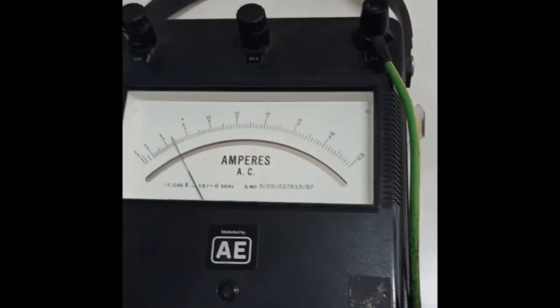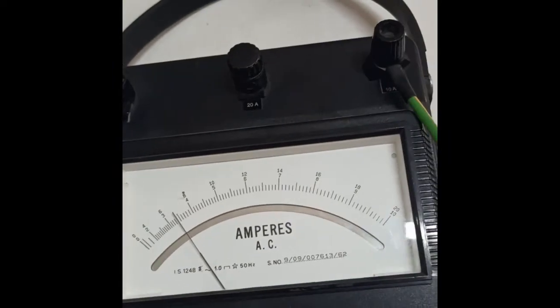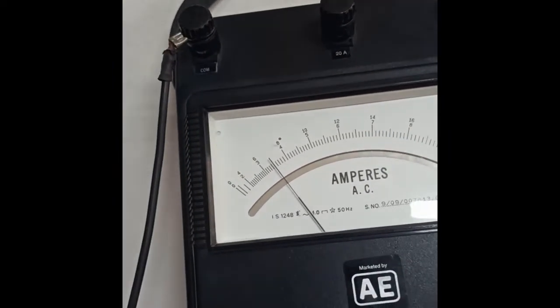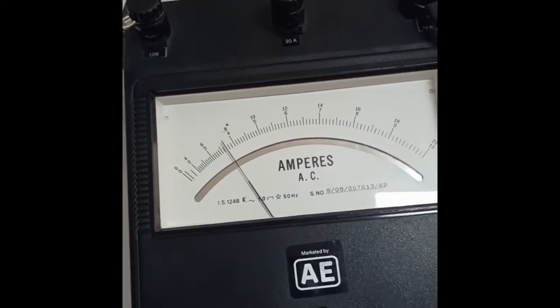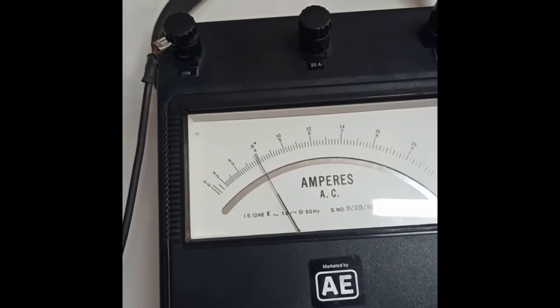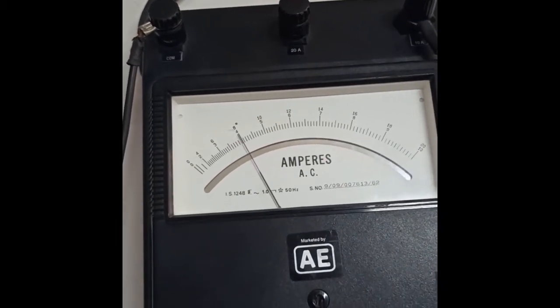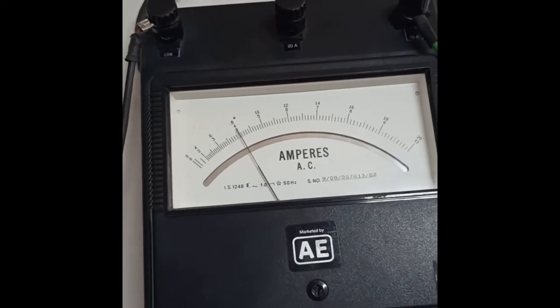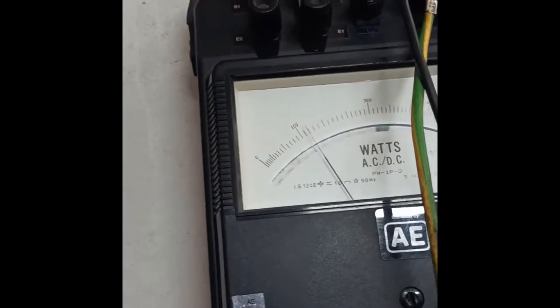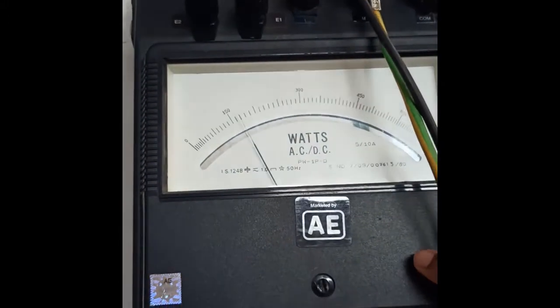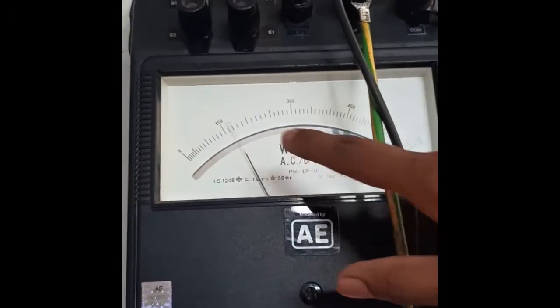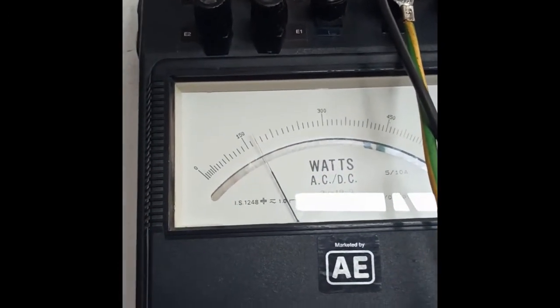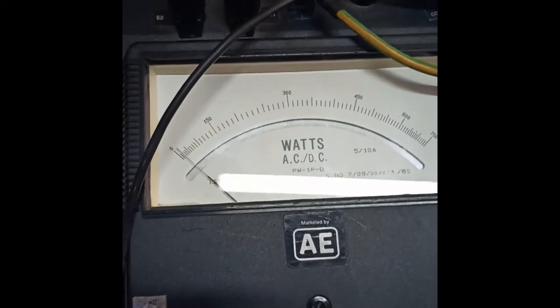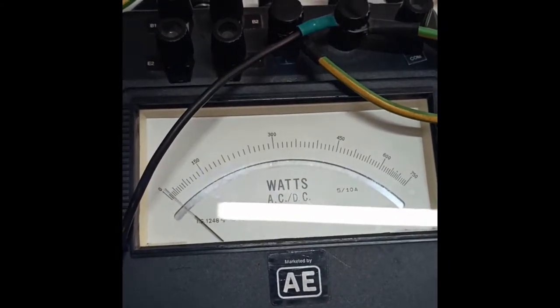Vary the load to adjust the current to 4 amperes. Now you can note down the readings. W1 is 165 watts whereas W2 is around 20 watts, but this is plus 20, the reading is positive.